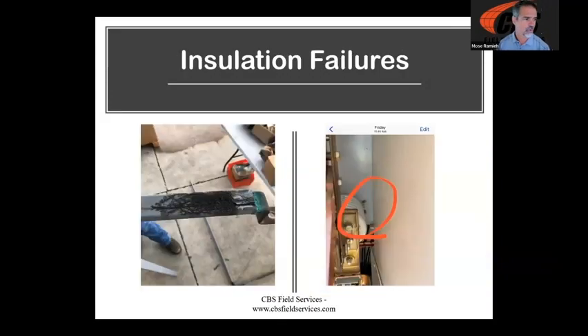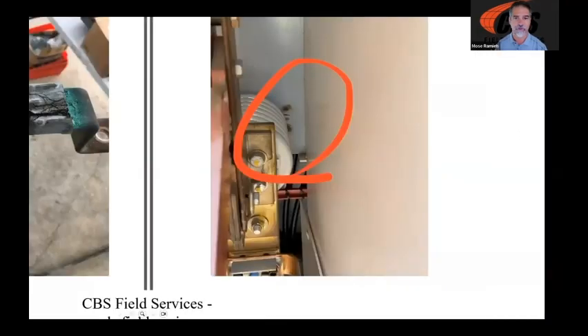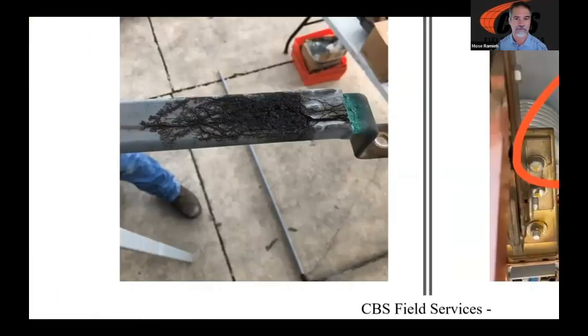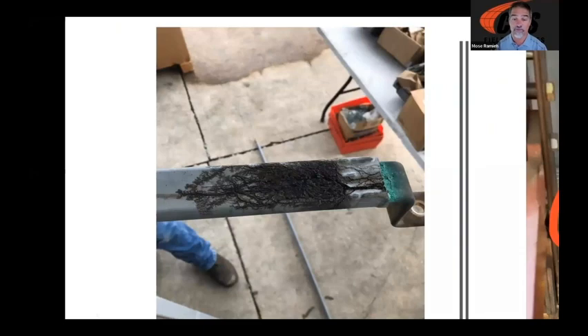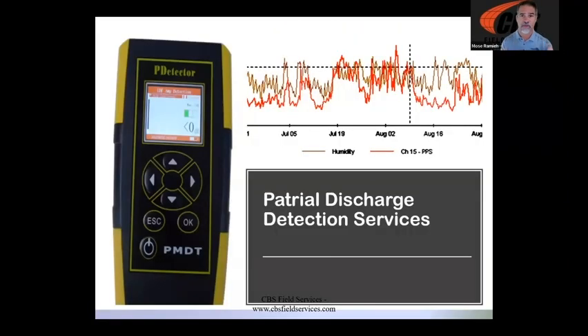All right, let's see, more routine inspections. Are we seeing any evidences of rust in our system? Rust is never good. This is almost always the case. We got partial discharge occurring. And once again, partial discharge left unaddressed can cause not only damage like we're seeing here, but ultimately catastrophic failure. Now, once again, you can't see that in most cases. You would need some form of partial discharge device to find that. And you got handheld units like the one pictured here.